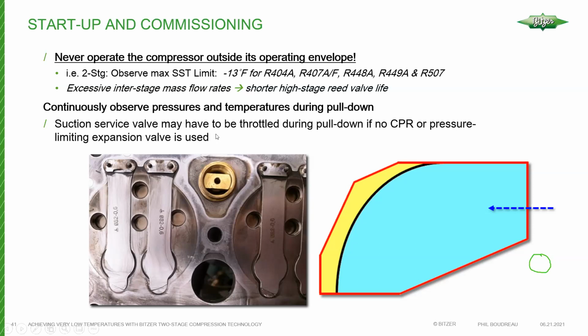But when you're running high saturated suction temperatures, it's very hard on the high stage in particular, and I guess to some extent the low stage, because you're outside the envelope. In the high stage, we have a very high mass flow rate. It's very hard on the reed valves. You can see the scores on these tips here, the reed valve tips where they drop into the cylinder and sit against the suction rest every time the piston is traveling downwards. They can actually break off.